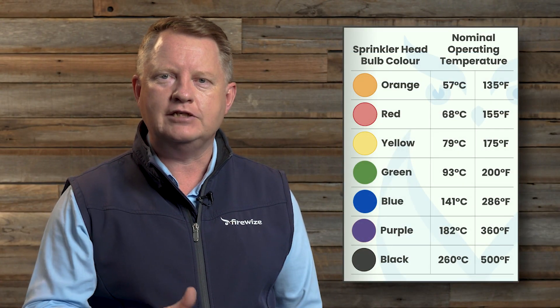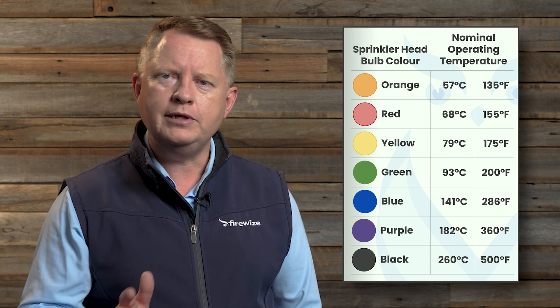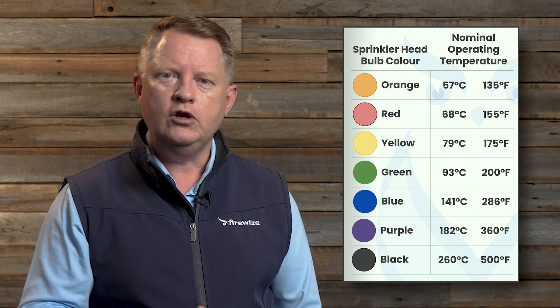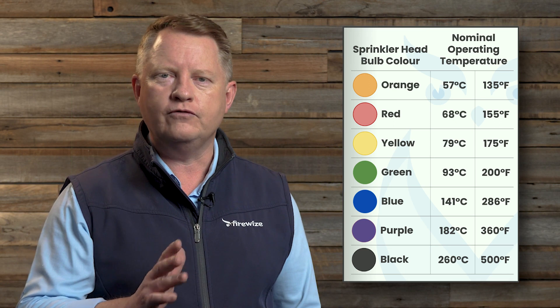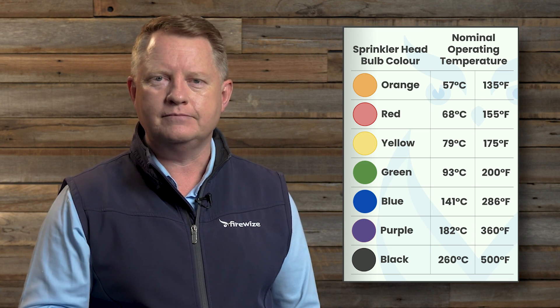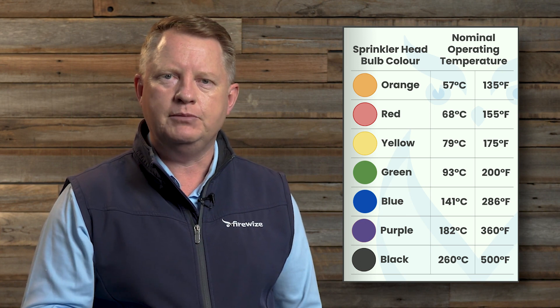The liquid in a frangible glass bulb of a sprinkler head contains either glycerin or alcohol mixed with a dye that indicates the activation temperature of the sprinkler head. There are seven common colours that describe the activation temperature, as shown in the illustration on the right. The most common colour you might see is red, which has a nominal activation temperature of 68 degrees Celsius or 155 degrees Fahrenheit. This is the most common colour for below ceiling applications in buildings.